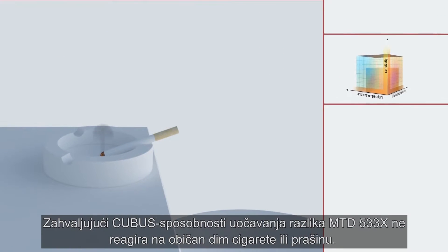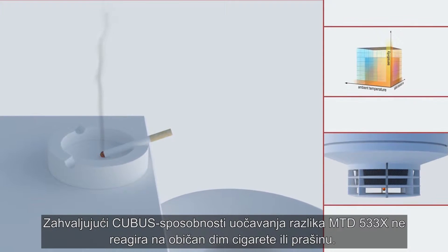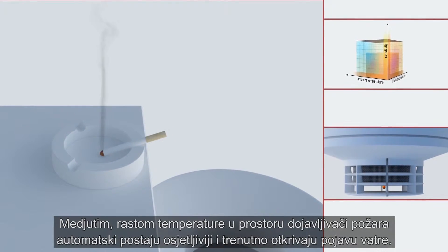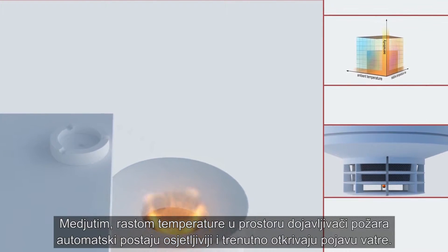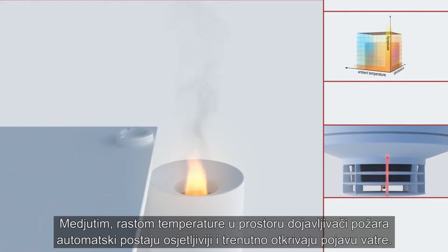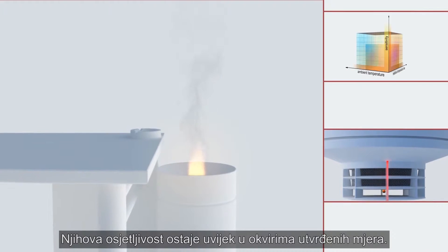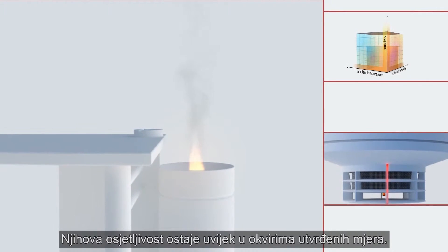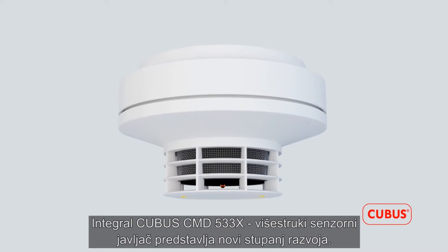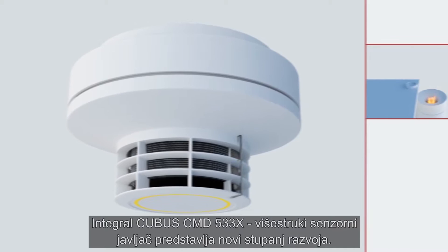Thanks to CUBUS' ability, the MTD533X simply filters out cigarette smoke or dust. If, however, in the event of a fire the room temperature increases, then the fire detectors automatically become more sensitive and detect a fire in seconds. The sensitivity of the detector, of course, always remains within the range set out in standards.